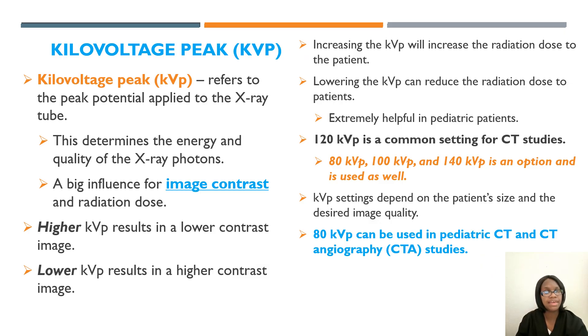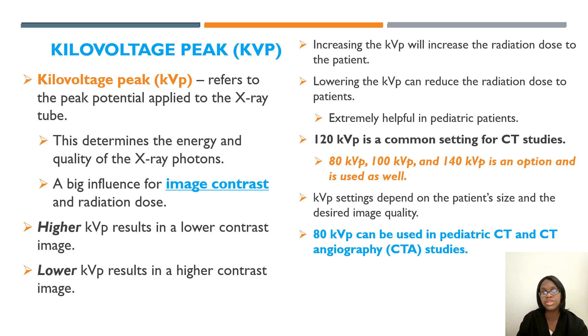Now we'll talk about kVp, or kilovoltage peak. This refers to the peak potential applied to the x-ray tube and determines the energy and quality of the x-ray photons — it is a big influence on image contrast and radiation dose. Higher kVp results in a lower contrast image; lower kVp results in a higher contrast image. Increasing the kVp will increase the radiation dose to the patient. Lowering the kVp can reduce the radiation dose to the patient.